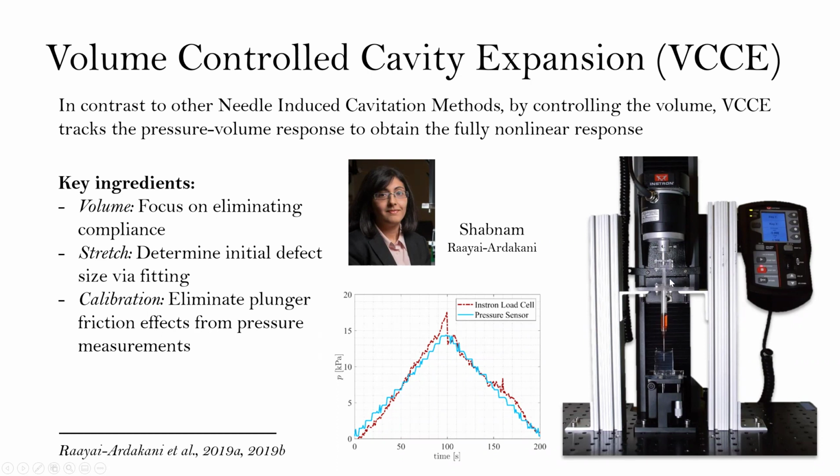our only measurement was this motion of the Instron and the applied force within the syringe barrel. And that required then calibration to remove the frictional force in order to actually understand from the measurement of the Instron what the pressure is inside the barrel. And that calibration is kind of what you see here.